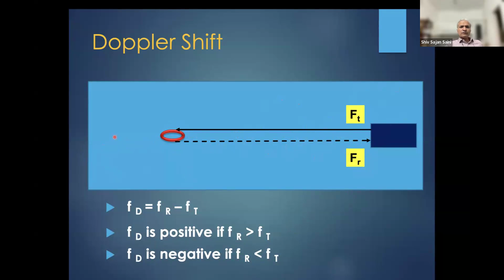So then the machine knows that if the Doppler shift is positive, which means the frequency of the received signal was higher, then the object must have been moving towards the ultrasound probe, right? And if the frequency of the received reflected wave is lower, then the object must be moving away from the probe. So because now there is a difference in the frequency, the machine knows whether the object is moving towards or moving away from the probe. Now this is the application. This is what is known as Doppler shift.